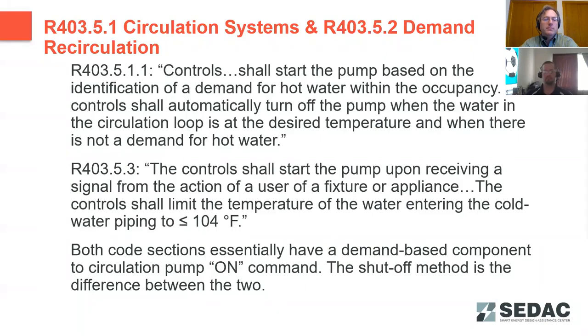So that is important to note that if you're going to install these in the building, you have to meet these requirements. That demand needs to be identified. And for demand recirculation systems, if you're using that cold water piping as your common return for hot water, you also need to shut off that pump when that cold water return line is 104 degrees or hotter. That way you're not overwhelming that cold water and still have immediate access to cold water supply as well.